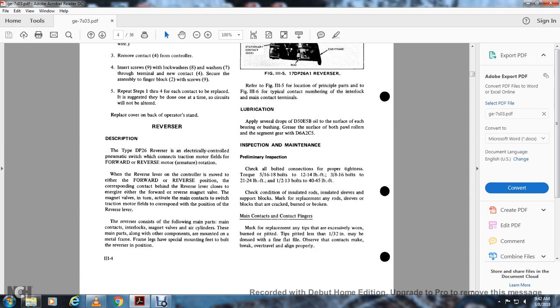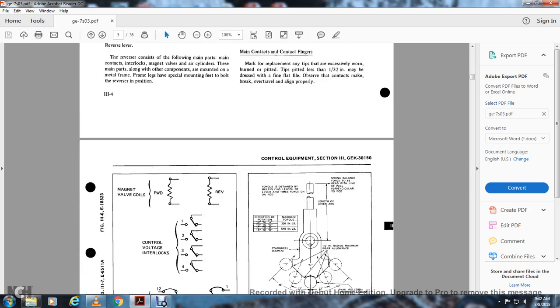Main contacts and contact fingers. Mark for replacement any tips that are excessively worn, burned, or pitted. Tips pitted less than 1/32 of an inch may be dressed with a fine flat file. Observe that contacts make, break, overtravel, and align properly.